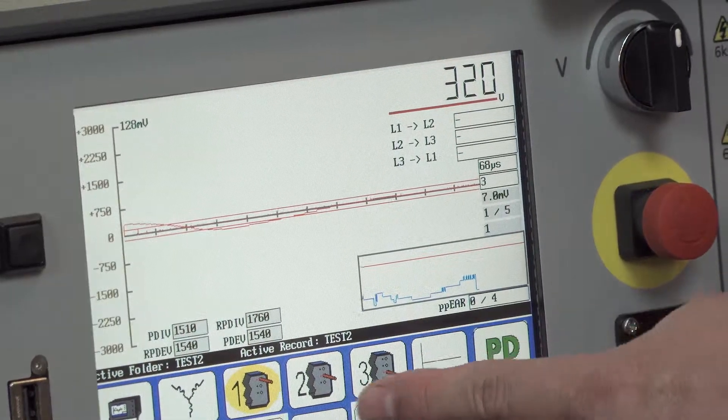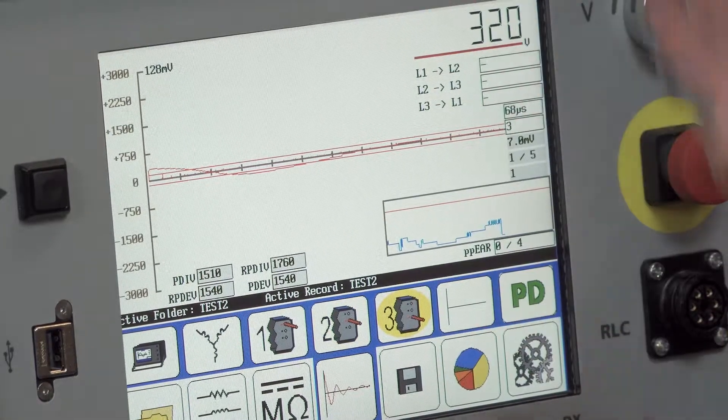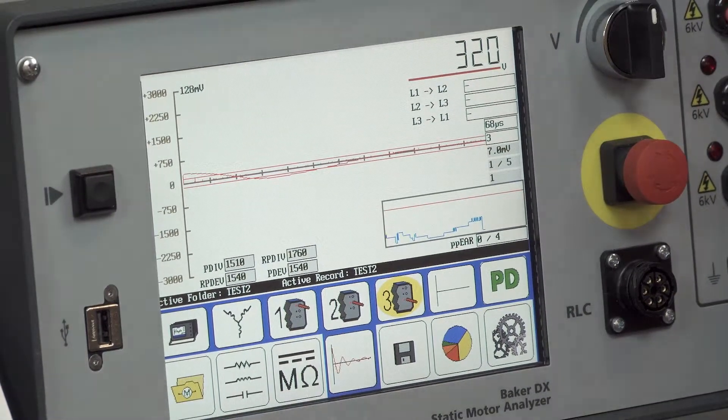And then we would proceed on with lead two in the same manner. Once complete, we would do lead three and we would record all the partial discharges for each of the phases of the motor.